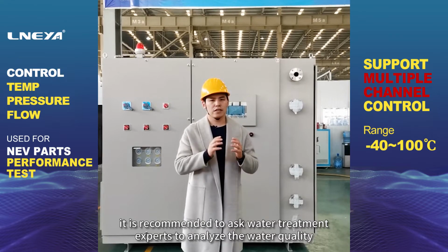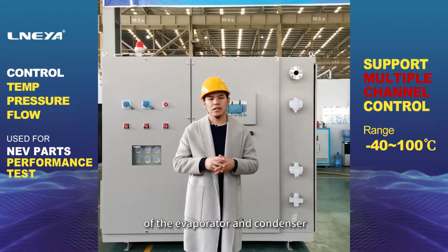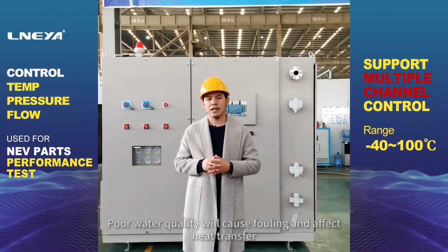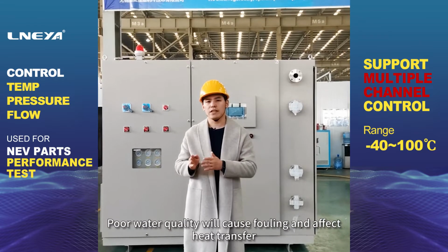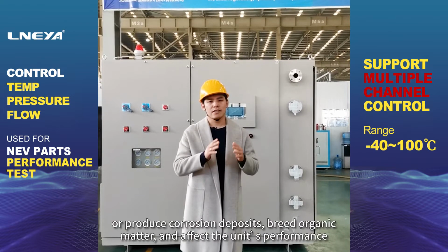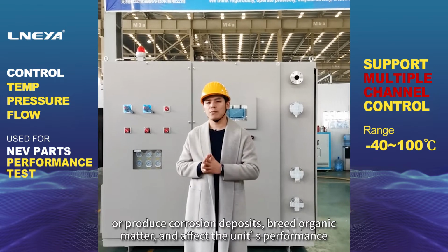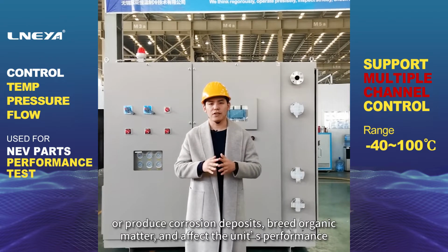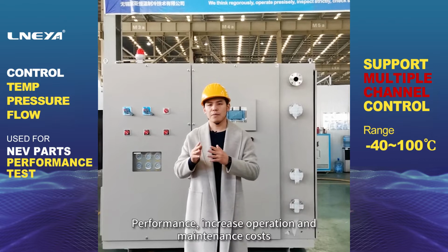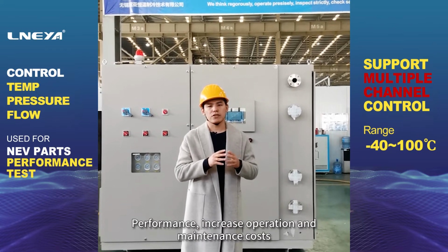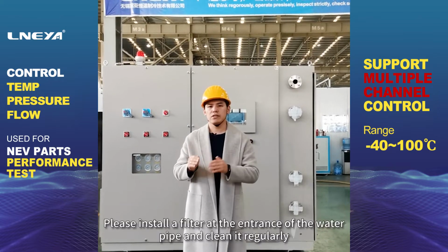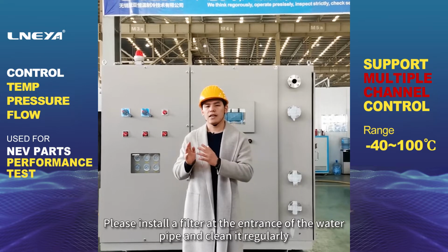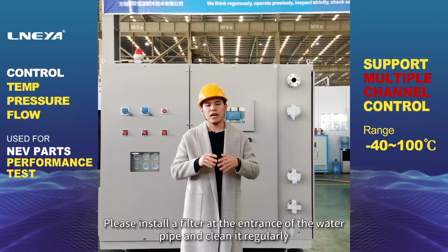water treatment experts to analyze the water quality of the evaporator and condenser. Poor water quality will cause fouling and affect heat transfer, or produce corrosion deposits, breed organic matter, and affect the unit's performance. Increase operation and maintenance costs. Please install a filter at the entrance of the water pipe and clean it regularly.